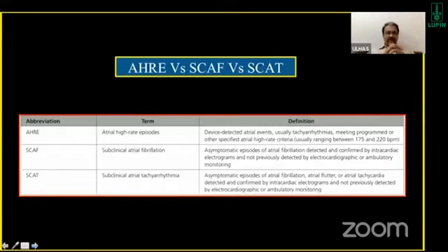After all, the device has its limited intelligence. It might have inappropriately considered a particular event as an atrial high rate episode. Then it would simply increase the AF burden. At the same time, even when there is indeed a high atrial rate episode, the device sensitivity is such that it may fail to detect the electrograms arising from the atrium, and then it may ignore them and falsely say the patient did not have a high atrial rate episode. So even though it is a good way, it has its limitations.